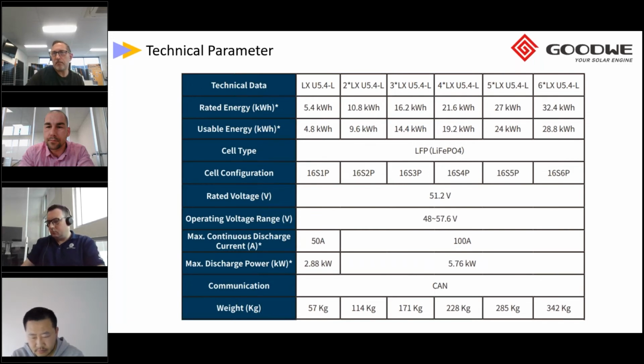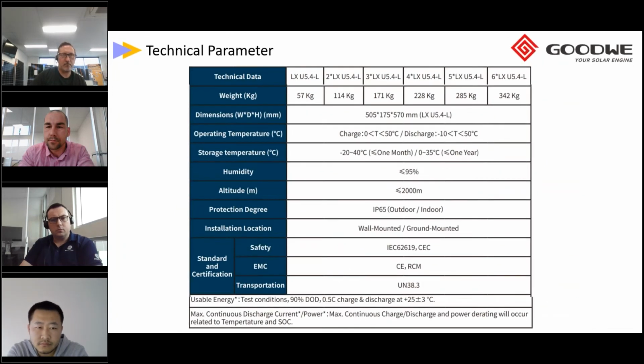Also, in most cases, people will couple two batteries together. That'll give them the 100 amps, maximum continuous discharge current. If you only use the one battery, it's a 50 amp max continuous discharge current, which effectively equates to a discharge power of 2.88 kilowatts. Whereas if they're using two batteries together, the max discharge power is 5.7 kilowatts. And each unit is 57 kilos each. As I said before, wall mounted, ground mounted, and it all comes in the box. There's nothing additional you need to purchase.